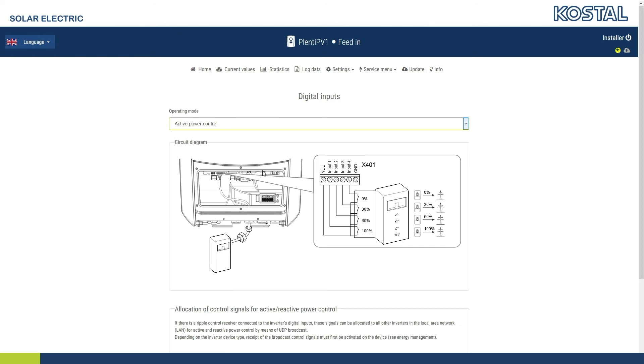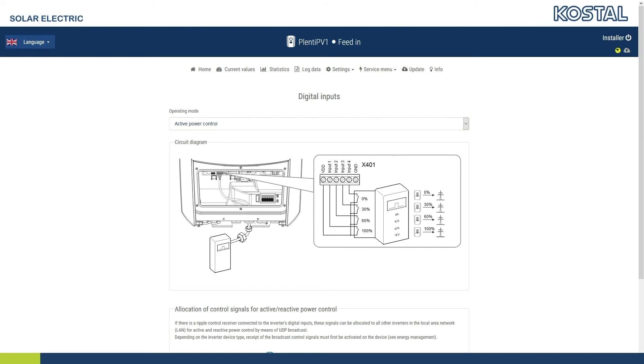If restriction on the feeding capacity using ripple control signal is stipulated for the PV system, the receiver needed for this can be connected to the digital inputs as shown in this connection diagram. If you are using several Kostal inverters, activate the distribution of the broadcast control signals. The corresponding command, for example shutdown all devices, is then sent to all devices present in the system by means of a broadcast via the network.